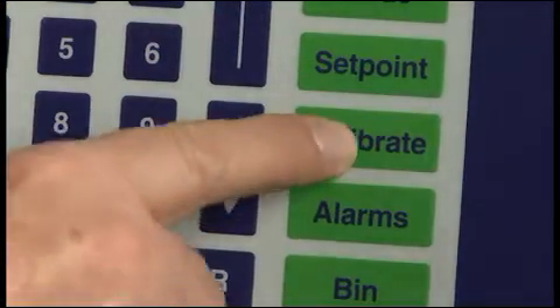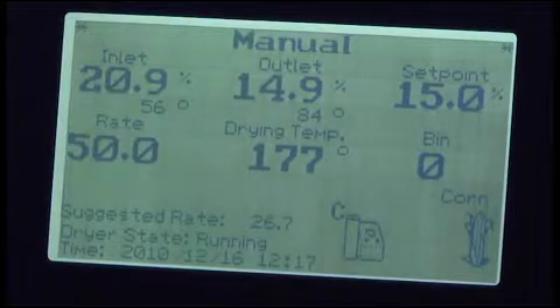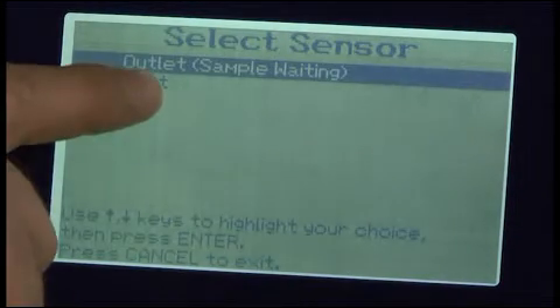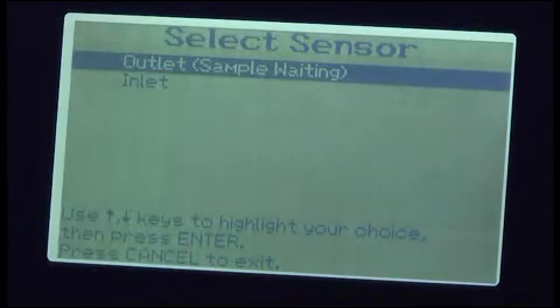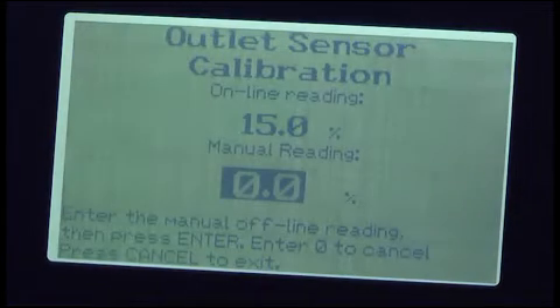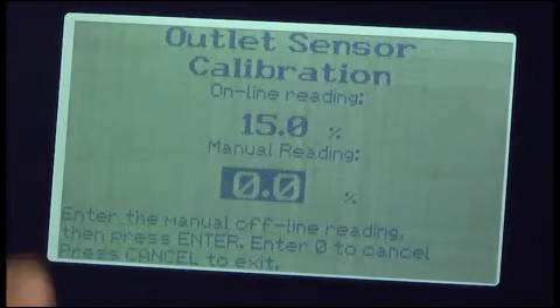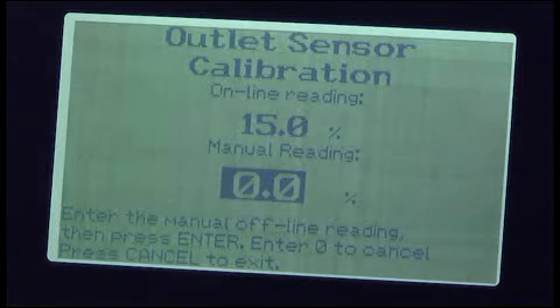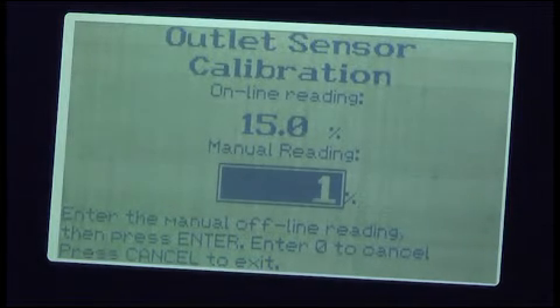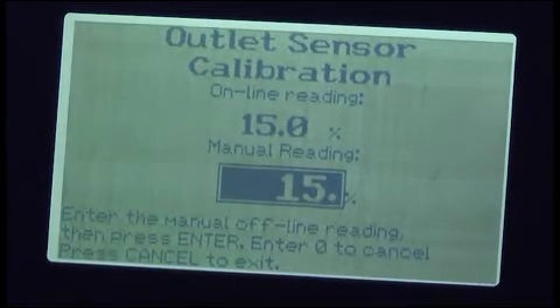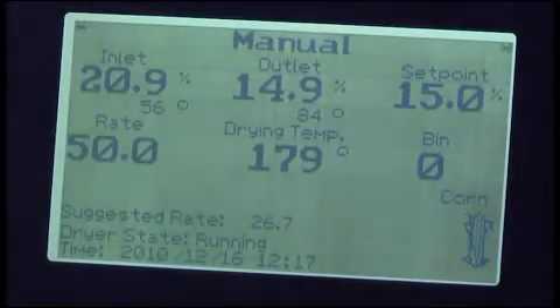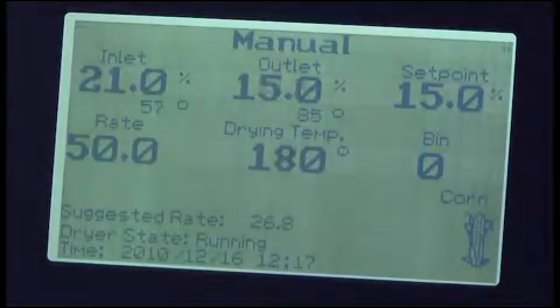F. Press the Calibrate button on the Dryer Master panel. G. Select the moisture sensor the sample is for. A sample waiting message will show in the line for the sensor to calibrate. H. Once selected, the moisture calculation will display. I. Enter your moisture value and press Enter. The Dryer Master will automatically update its moisture calculation formula.